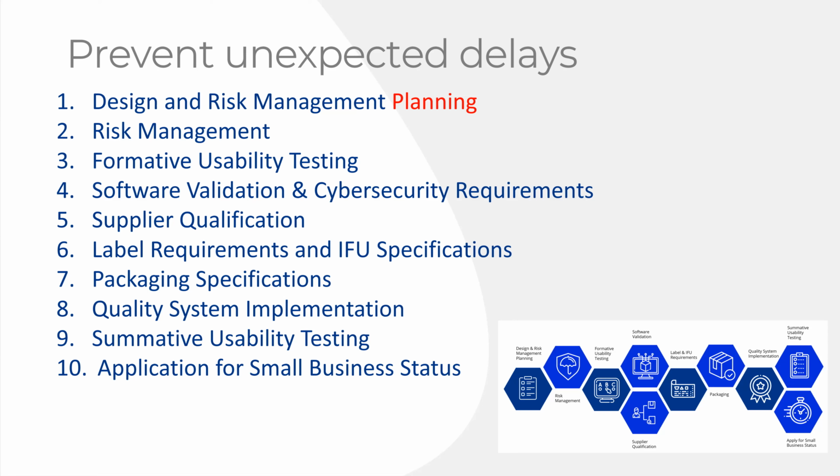So you need to actually know exactly what the FDA is looking for now on the summative usability testing, not what's in the guidance from 2016. It's been 6 years. They've changed what they're looking for, and they haven't updated the guidance. And that may not be fair, but that's how things work at the FDA right now.